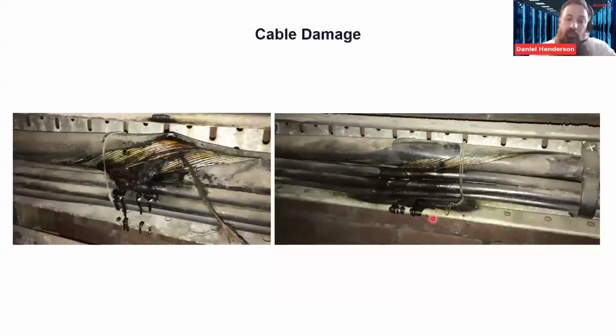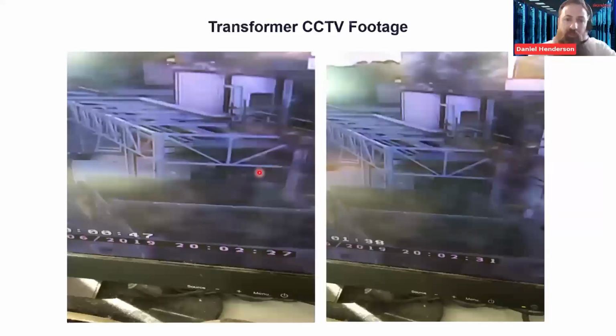The cable from that junction box on the switchgear to the transformer was around 100 meters, roughly, and it was like this all the way down. So that's an immense amount of heat that's gone through that to actually split the cable all the way down. That was the full length, full 100 meters. So quite a lot of damage. And then we've now got power back.